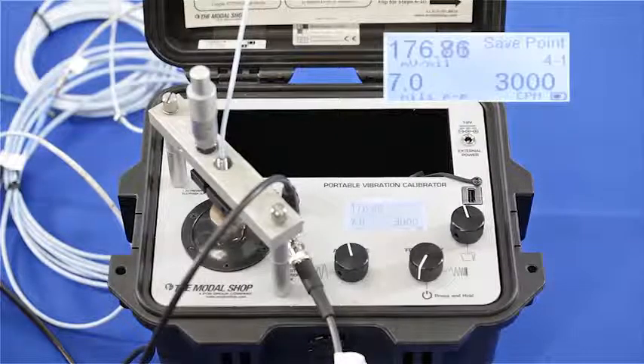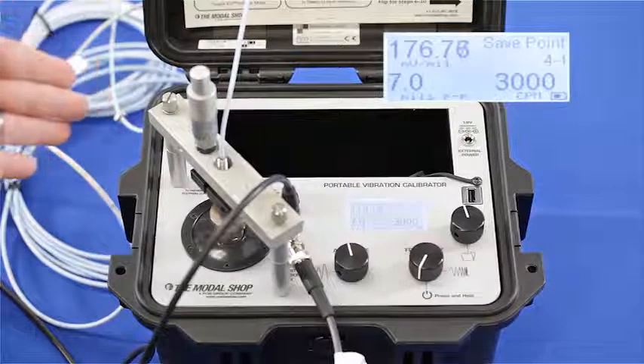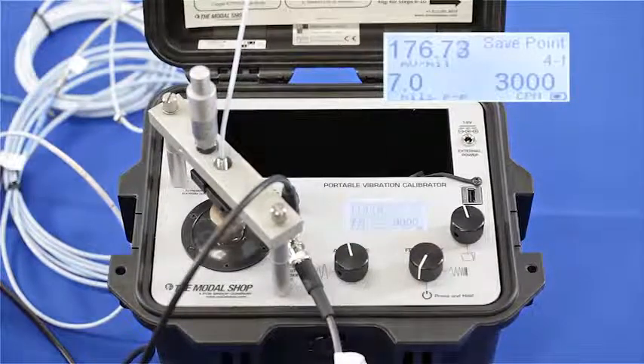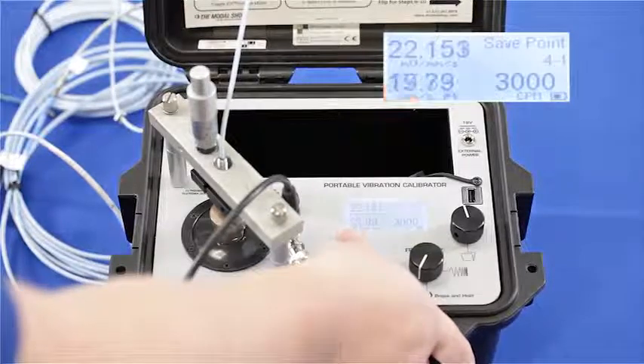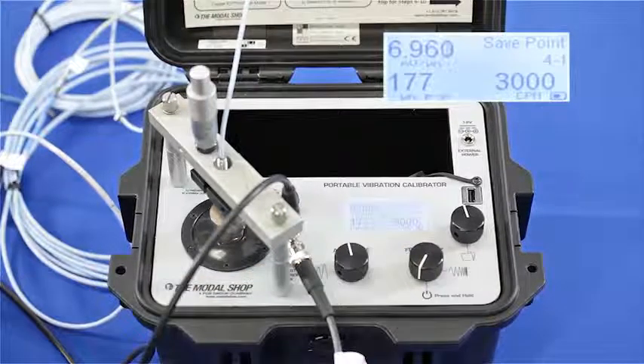Now I've thrown my system off by connecting a 4.5-meter extension cable to my proximity probe that already has 1 meter of cable. So I'm sending 5.5 meters of cable to a 5-meter system. And you can see, calibrating at the exact same displacement, 7 mils peak to peak and 3,000 CPM, I'm at about 177 millivolts per mil. Or in microns, the output is 6.96 millivolts per micron.